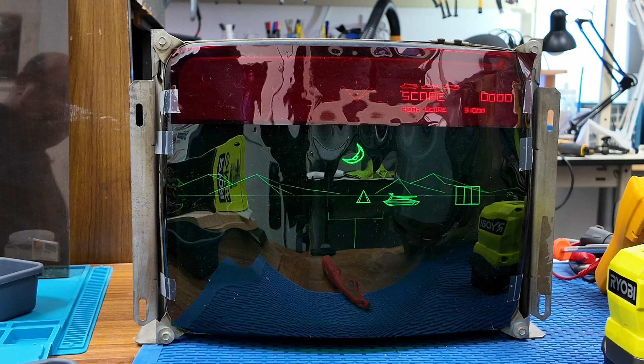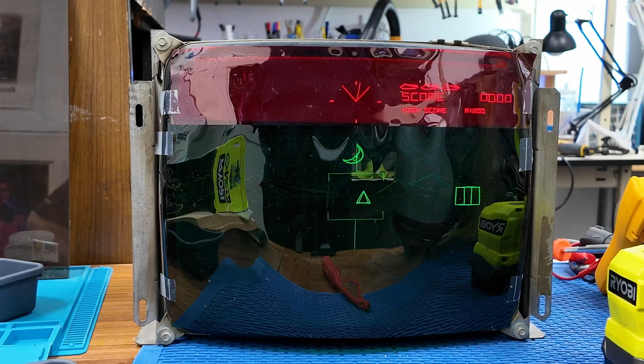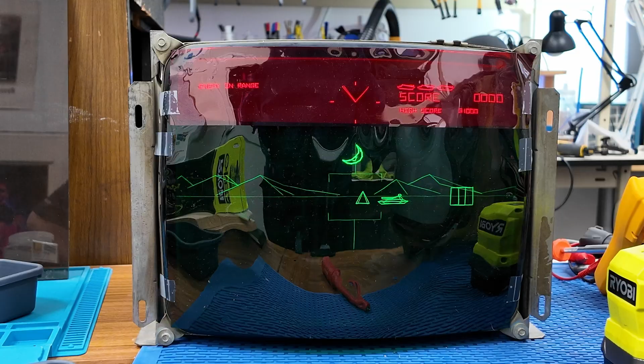All right, we have the high voltage board back in the monitor. I'm not seeing any significant change in the brightness problem, so it doesn't look like the issue is due to a bad solder joint, or at least not with the ones that I replaced. So I thought we'd stop here and review what we found so far, what's been fixed, and what are some of the possible remaining causes of the dim image.